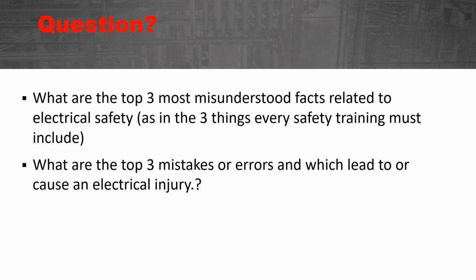All right, another one. When I'm teaching, what I've even started doing the last several years is doing hands-on training. I'll have a seminar one day, and the next day I'll do hands-on training. One of the things that is probably the most forgotten step is after you have tested it, and this is testing for the absence of voltage, and it's sometimes called live-dead-live test. You test for the absence of voltage. You test the tester to begin with on any known energized source.